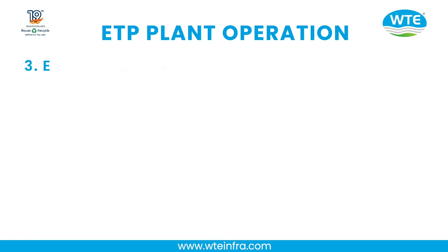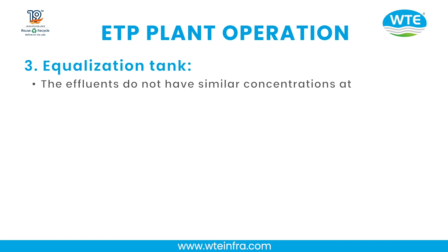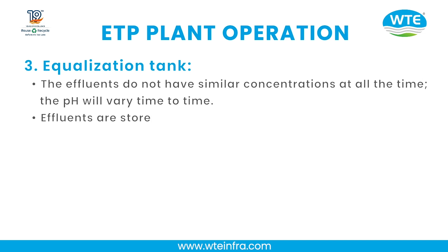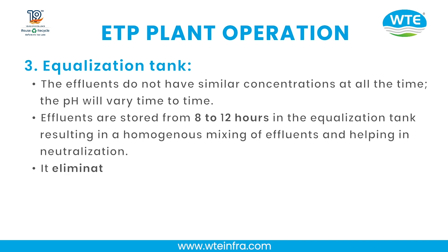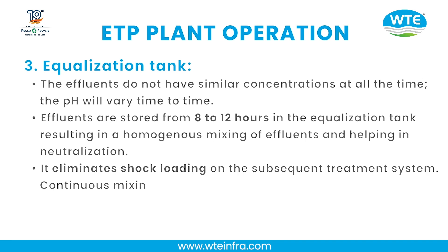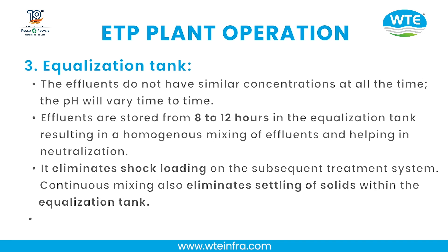Step 2 — Collection Tank: The collection tank collects the effluent water from the screening chamber, stores it, and then pumps it to the equalization tank. Step 3 — Equalization Tank: Effluents do not have similar concentration at all times, and pH varies over time. Effluents are stored for 8 to 12 hours in the equalization tank, resulting in homogeneous mixing and helping with neutralization. It eliminates shock loading on the subsequent treatment system. Continuous mixing also eliminates settling of solids within the equalization tank.